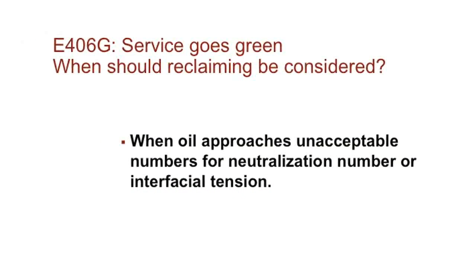The benefits are we use the natural core losses, the heat of the transformer as it's energized, to help heat the transformer, and it helps naturally flush the transformer and process the oil through the winding as the reconditioning is taking place. Offline, we have to bring in a portable set of heaters to bring the oil temperature up to the desired temperature during the filtering process in order to extract the moisture and contamination out of the oil. When should reclaiming be considered?